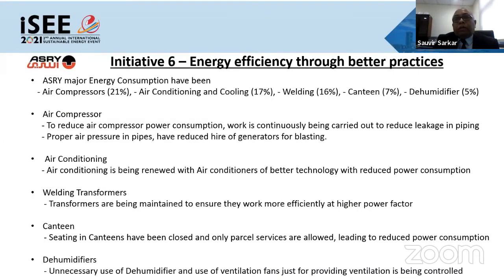Our audit results showed air compressors had a large energy load, along with air conditioning, welding, and the canteen. For air compressors, the issue was primarily leakages at various locations, which meant we used to hire generators when air pressure was too low to cater to blasting requirements. Now we have good preventive maintenance ensuring all lines are tight, which has allowed us to stop hiring generators for blasting.